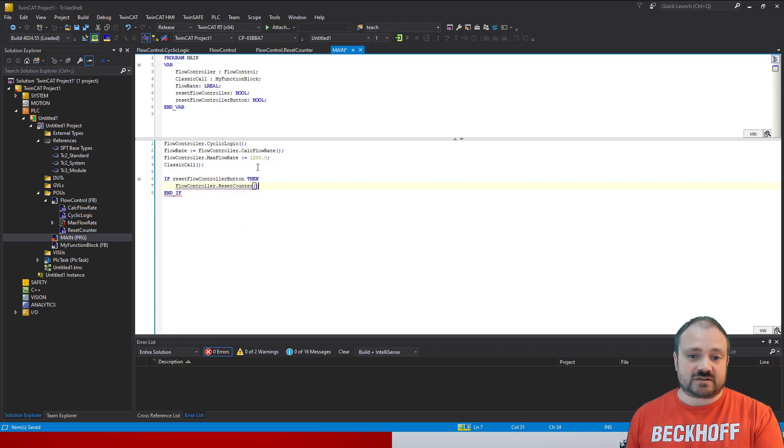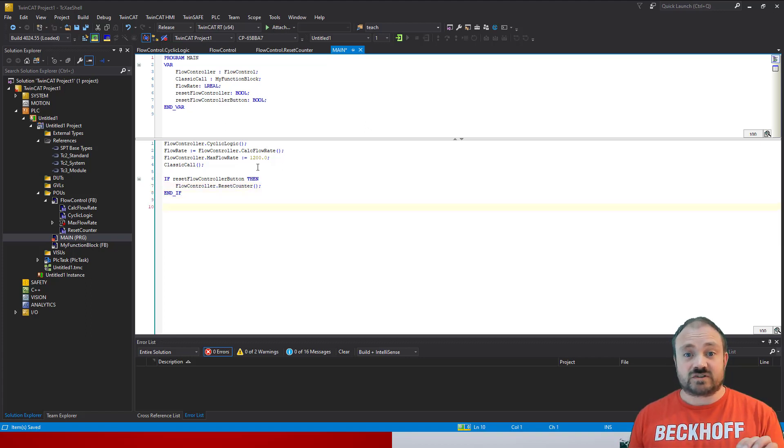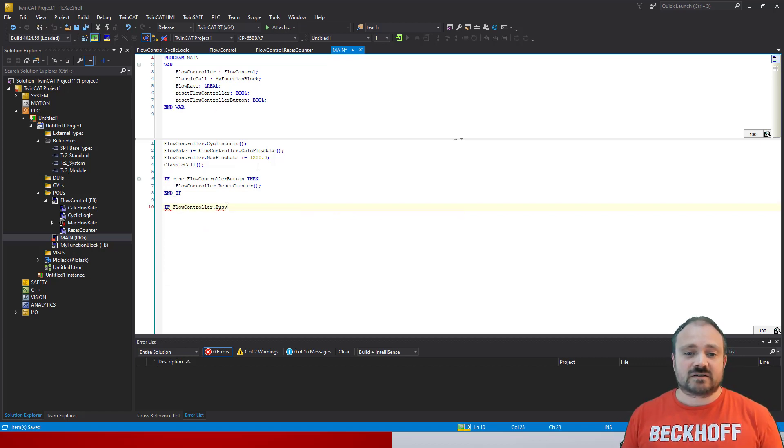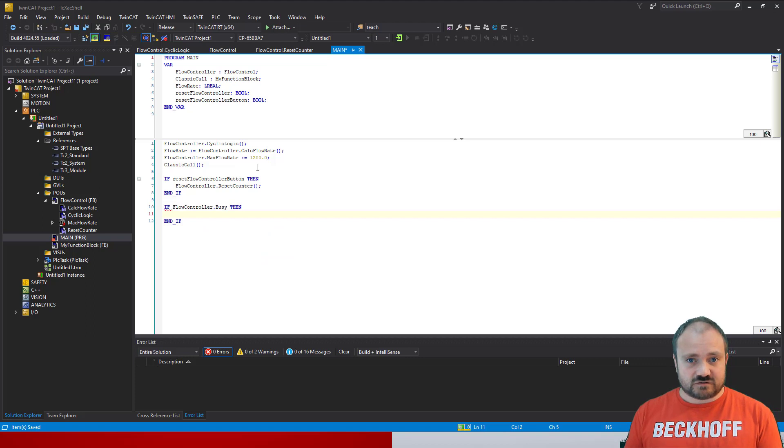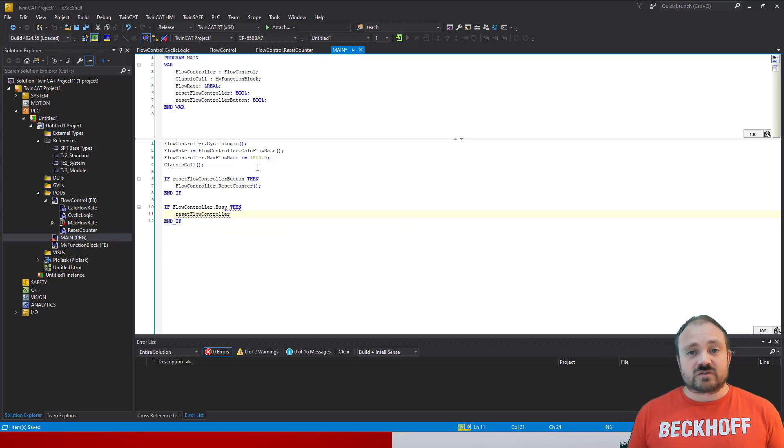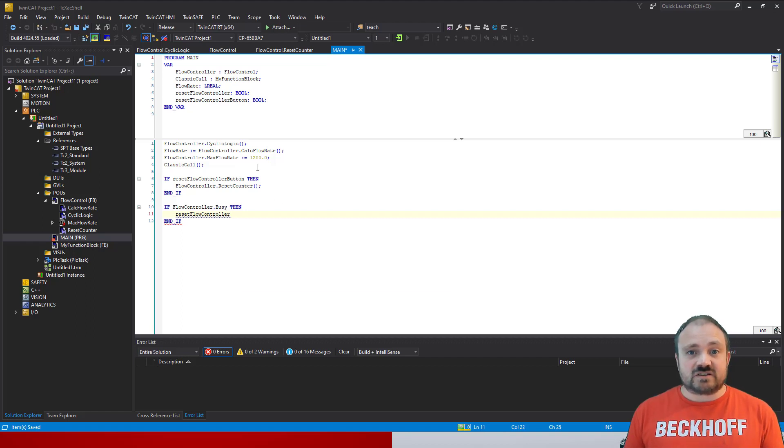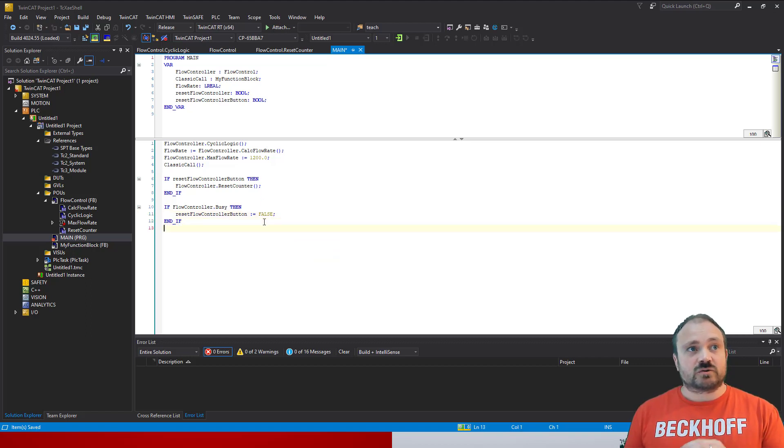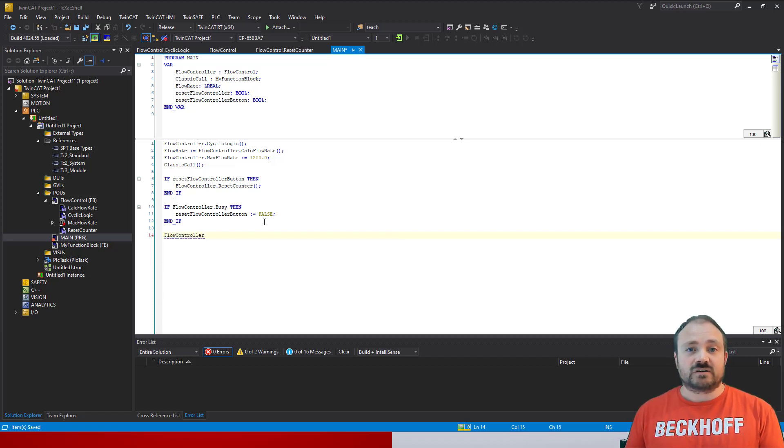Then it will clear that button command coming in from the main program. So hit the button to reset the counter, calls the reset counter, triggers our flow controller to do its behavior. And by watching the status flags coming back, so this busy and error flags that we have, we can then determine if what the state of our component is in. Okay, so we can then make decisions based on if it's busy. Obviously this forces you into a path where you declare things as busy or not busy, so there's no done flag.